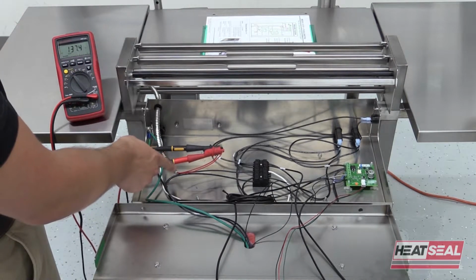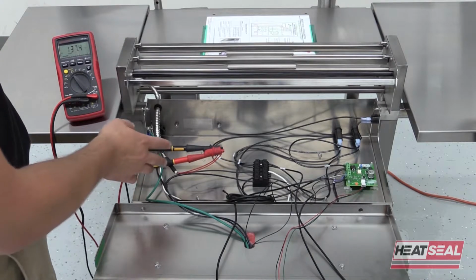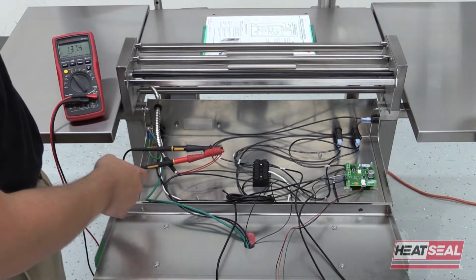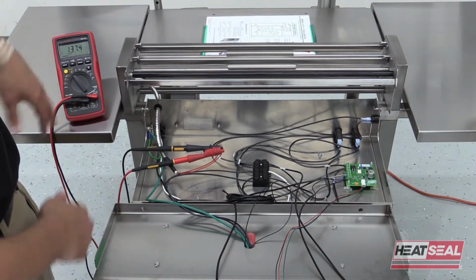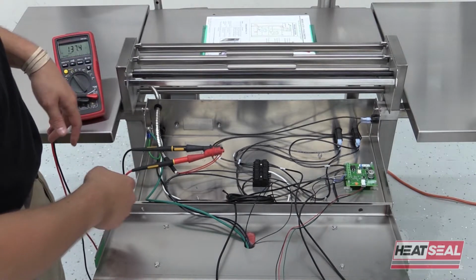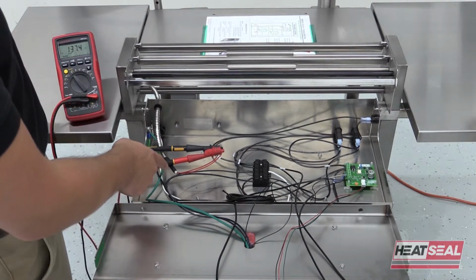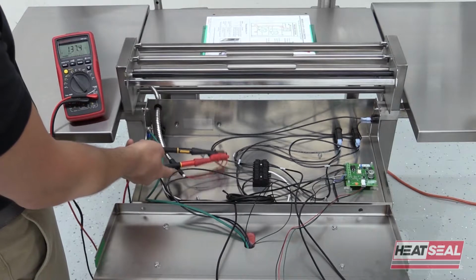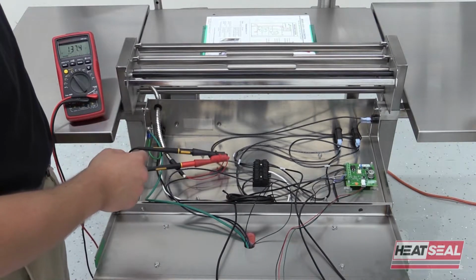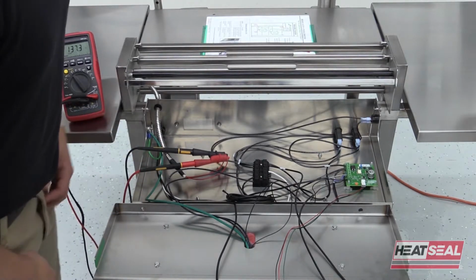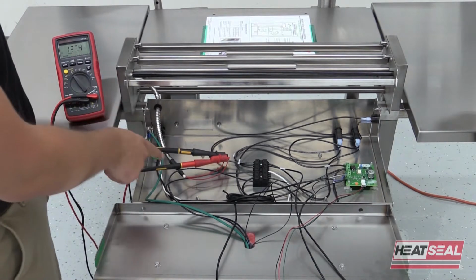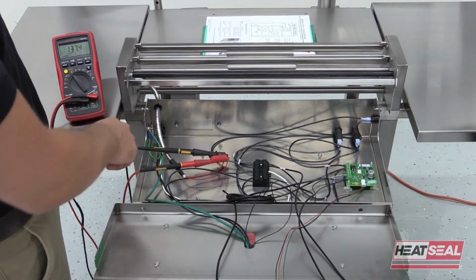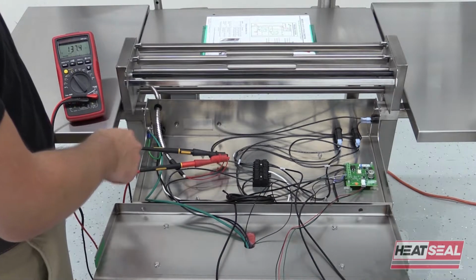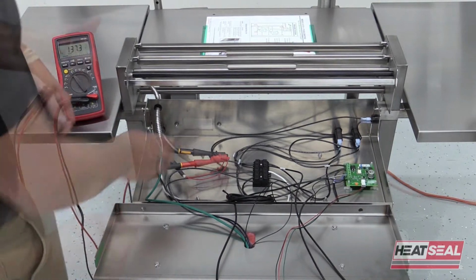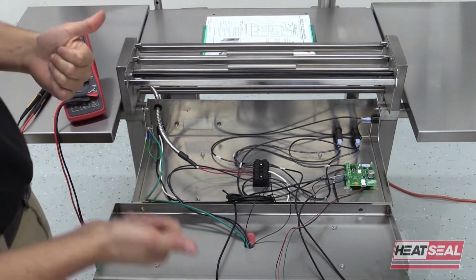For the armored cable hot rod, you're going to want to see between 130 to 140 ohms. In this case, this one's around 137. And for the hot rod that has the black heat shrink tubing, you're going to want to see about 260 to 270 ohms.